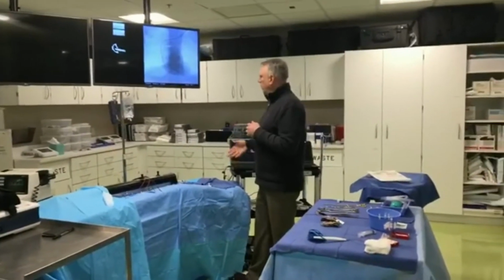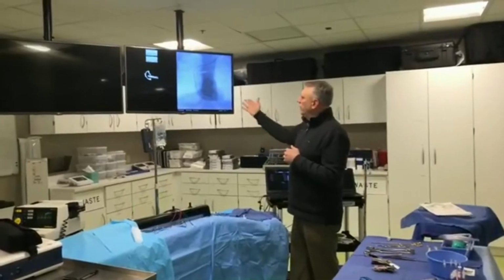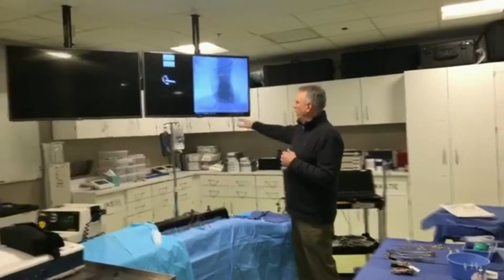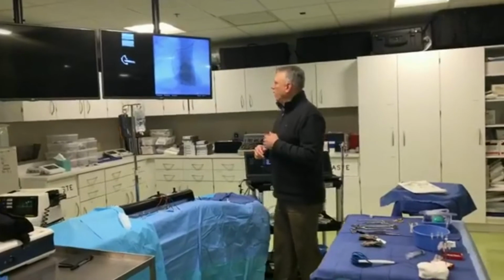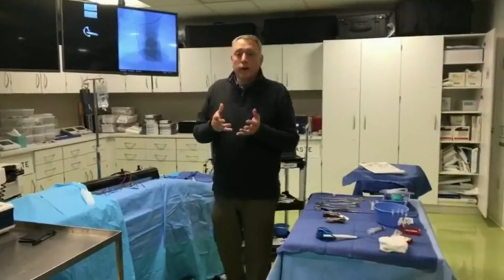As I step on the pedal here, I don't know if you can tell from the video, the heart actually starts beating, replicating a fluoro. You can see that lead moving back and forth. So we've got 2 wires, or what we call leads, actually inside the patient's heart. One in the patient's ventricle, or the bottom chamber of the heart, and another one in the atrium. And this particular system is designed to defibrillate a patient if they were to have a life-threatening arrhythmia.